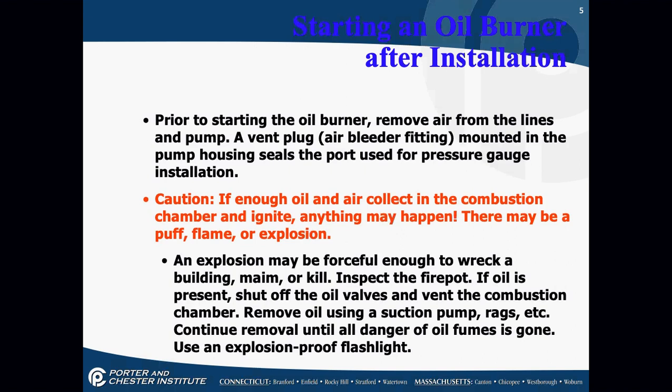Prior to starting the oil burner, you want to remove the air from the lines and pump. There's an air bleed fitting mounted on the pump housing, which is also used for pressure gauge installation. If enough air and oil collect in the combustion chamber and ignite, there could be a puff of flame or an explosion — make sure you don't let a lot of unburnt fuel into the combustion chamber. An explosion can be forceful enough to wreck a building. Inspect the fire pot, which is the combustion chamber. If oil is present, shut off the oil valves and vent the combustion chamber. You can remove excess oil using a pump or rags; continue removal until all danger of oil fumes is gone.